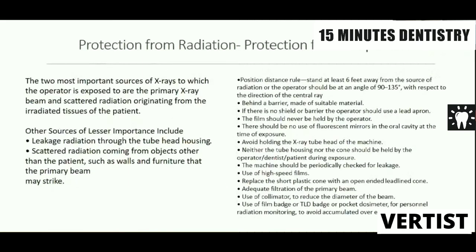Protection for the operator: leakage radiation comes through the tube head housing and scattered radiation comes from irradiated objects. Using the position-distance rule, stand six feet away from the source of radiation. Stand behind a barrier; if there is no shield, use a lead apron. The film should never be held by the operator. Do not use fluorescent mirrors in the oral cavity while taking radiographs. Avoid holding the tube head — neither the tube housing nor the cone should be held by the operator. The machine should be periodically checked. Use high-speed films, replace the plastic cone with an open-ended lead-lined cone, and use added filtration, a collimator, and a TLD badge to monitor radiation exposure.